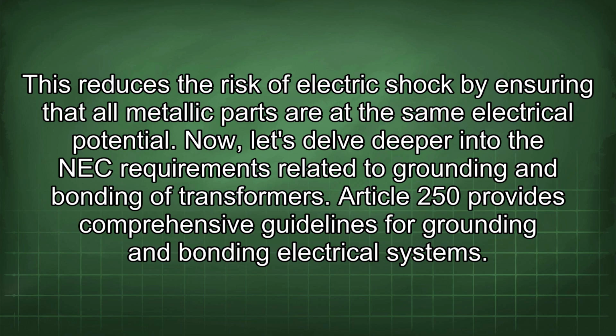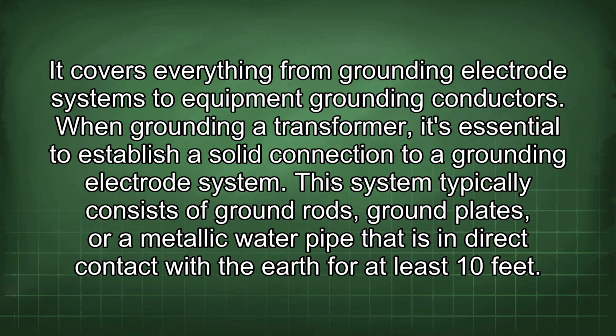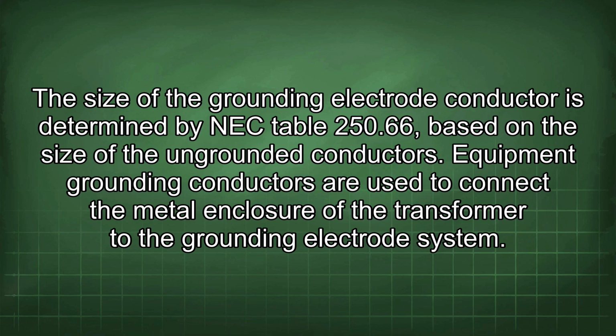Now let's delve deeper into the NEC requirements related to grounding and bonding of transformers. Article 250 provides comprehensive guidelines for grounding and bonding electrical systems. It covers everything from grounding electrode systems to equipment grounding conductors. When grounding a transformer, it's essential to establish a solid connection to a grounding electrode system. This system typically consists of ground rods, ground plates, or a metallic water pipe that is in direct contact with the earth for at least 10 feet. The size of the grounding electrode conductor is determined by NEC Table 250.66, based on the size of the ungrounded conductors.